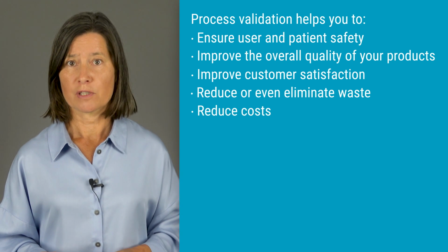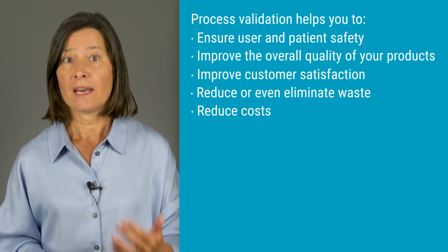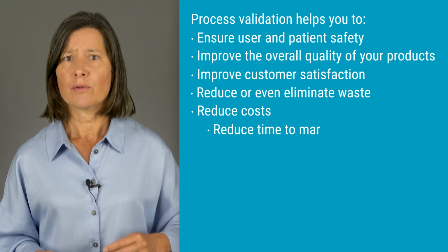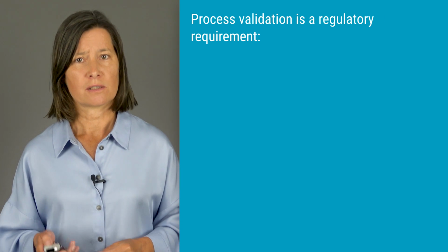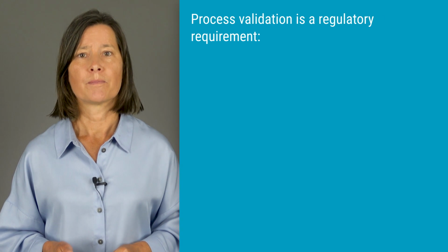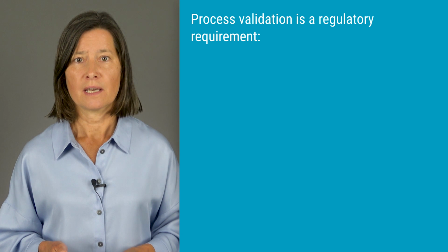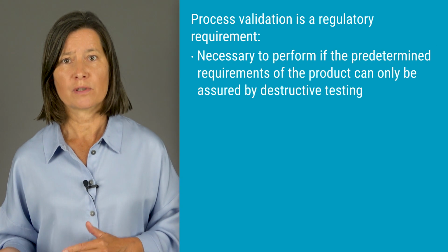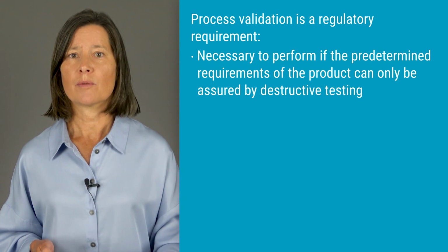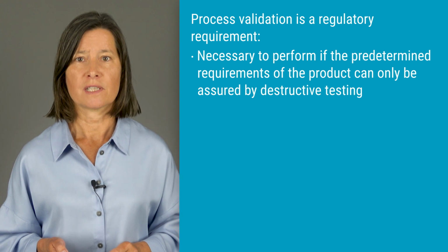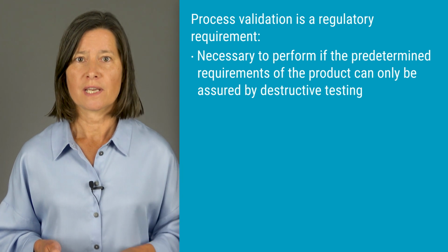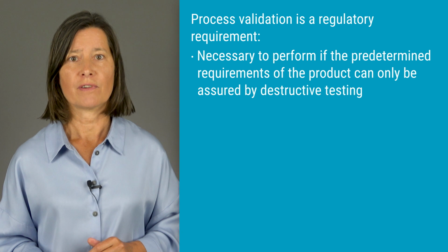And by performing process validation correctly and at the right time, it may even reduce time to the market for new products. Apart from the already mentioned reasons, process validation is also a regulatory requirement. As already stated, it is necessary to perform process validation if the predetermined requirements of the product can only be assured by destructive testing, which is another way of saying that the requirements cannot be verified.